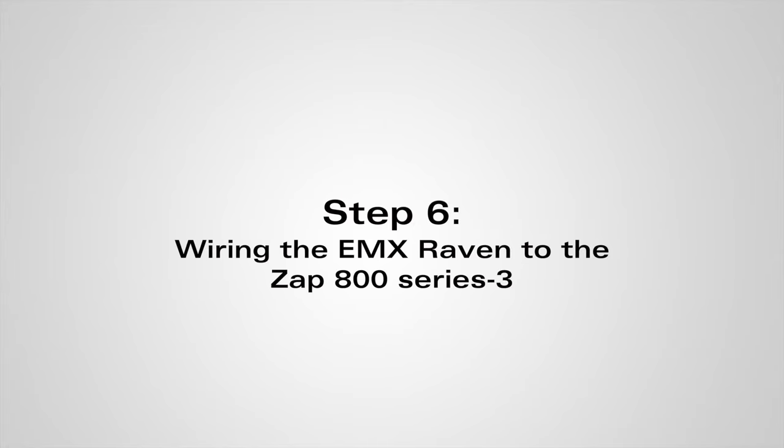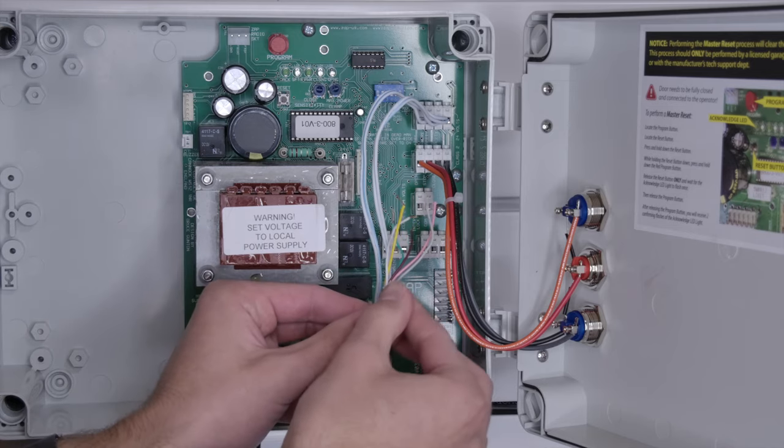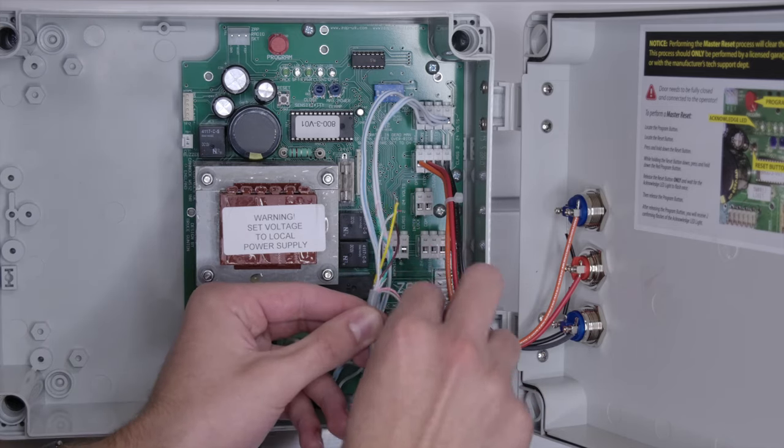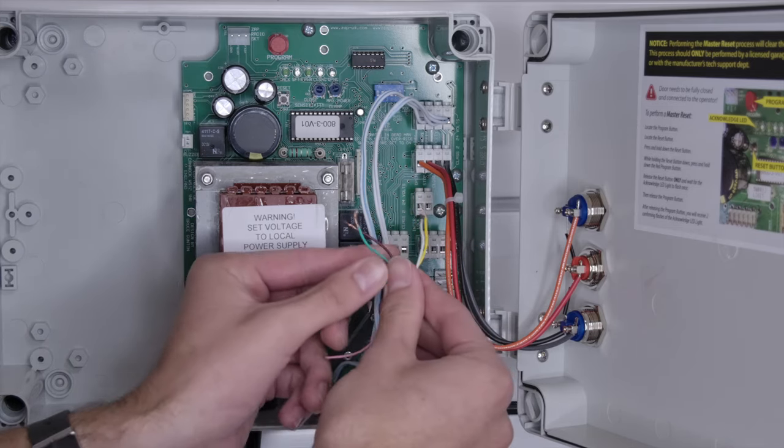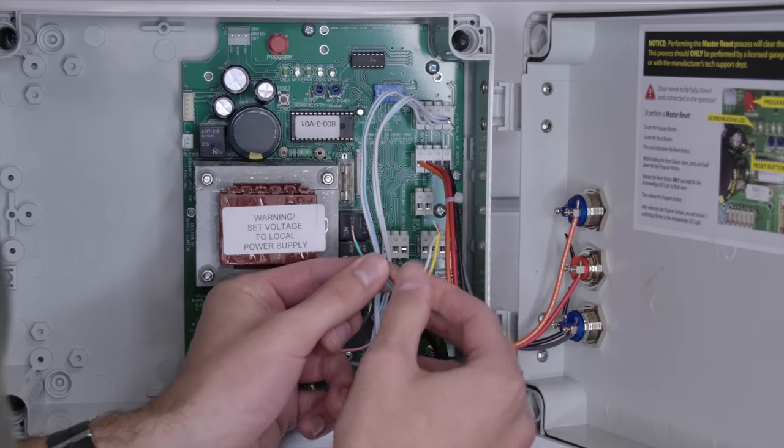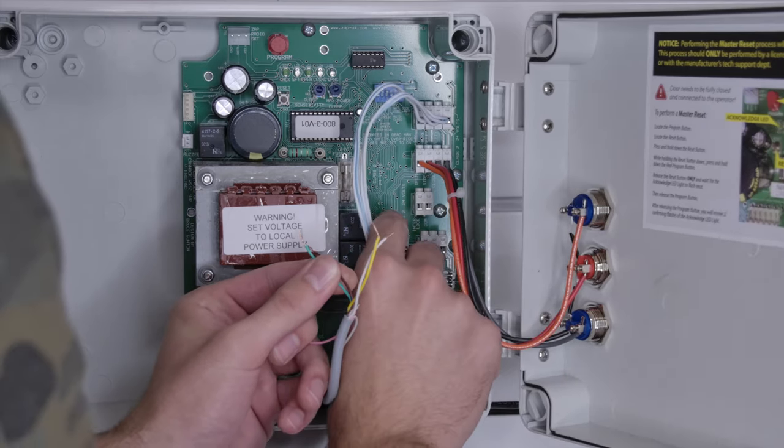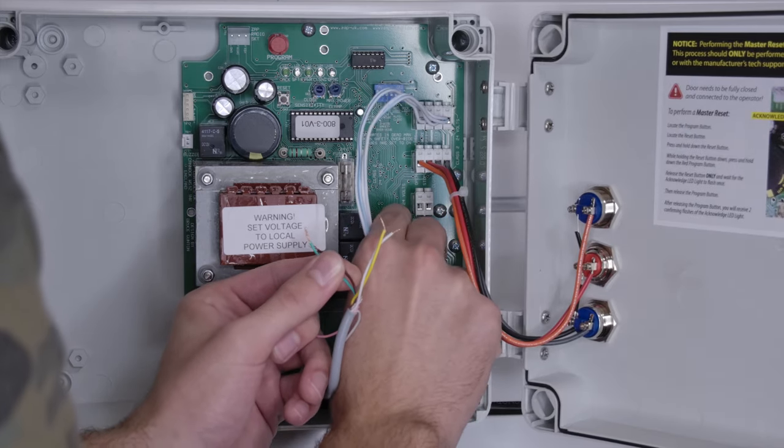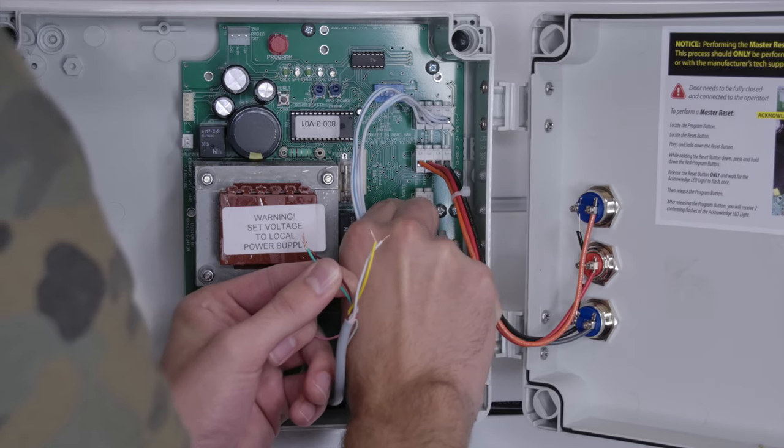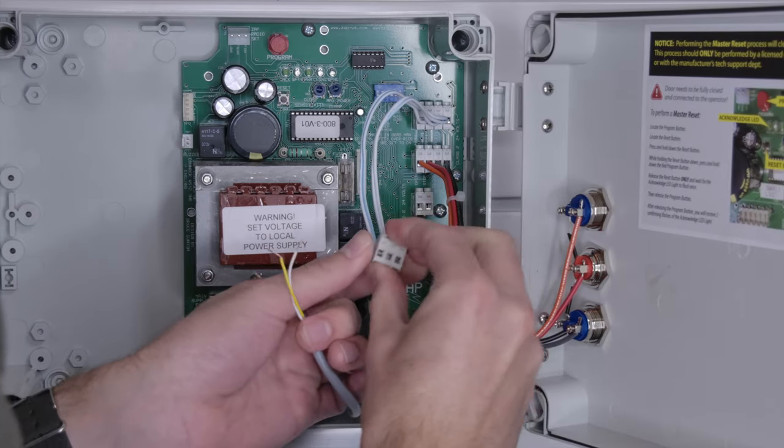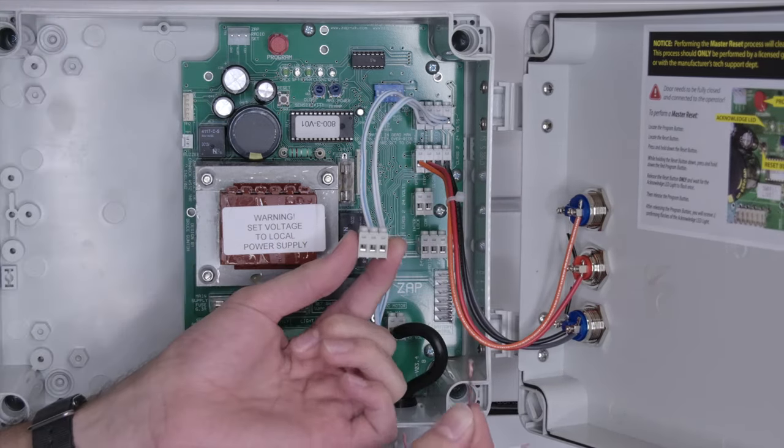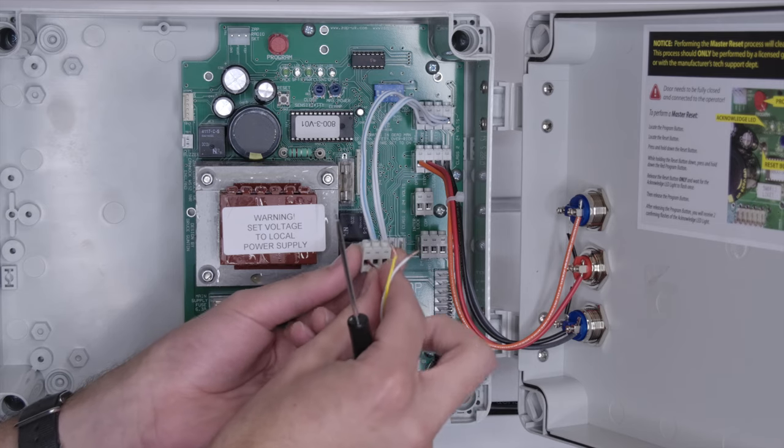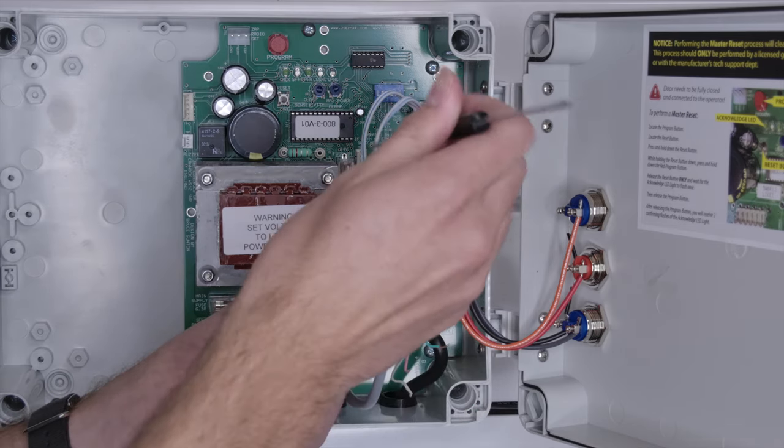To wire the sensor to the control box, feed it through the bottom. You will not be needing the pink or gray wire, only the brown and green and yellow and white. The brown and green wires will go in the plug for power. The brown wire goes in the opening labeled 24 volts and the green wire goes in the 0 volt opening.